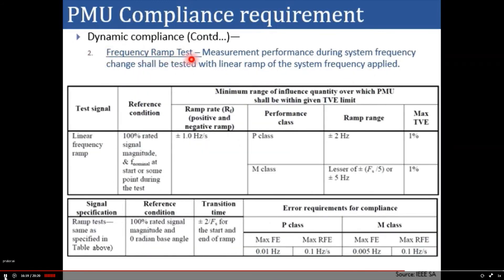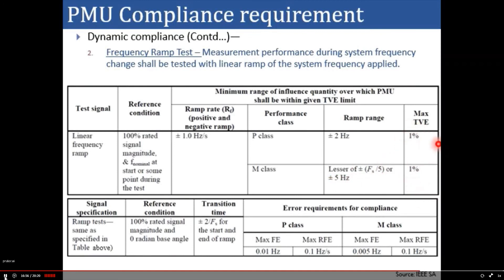For the frequency ramp test, measurement performance during frequency change is tested using a linear ramp of 1 Hz per second (ramp up and ramp down). For P class, the ramp range is ±2 Hz; for M class, it is the lesser of ±(frame reporting rate / 5) or ±5 Hz. In both cases, TVE should be ≤1%. For M class, the maximum frequency error is 0.005 Hz and the maximum ROCOF error is 0.1 Hz/s.